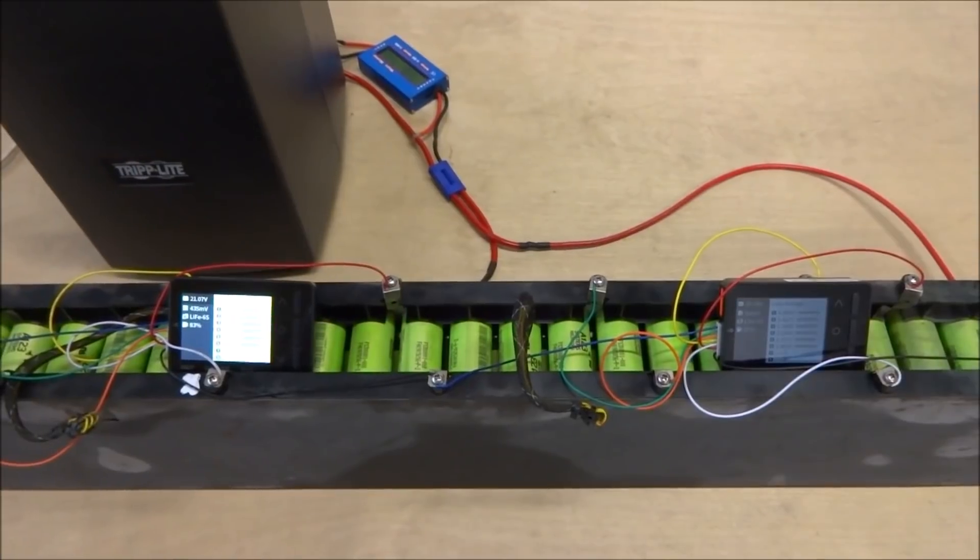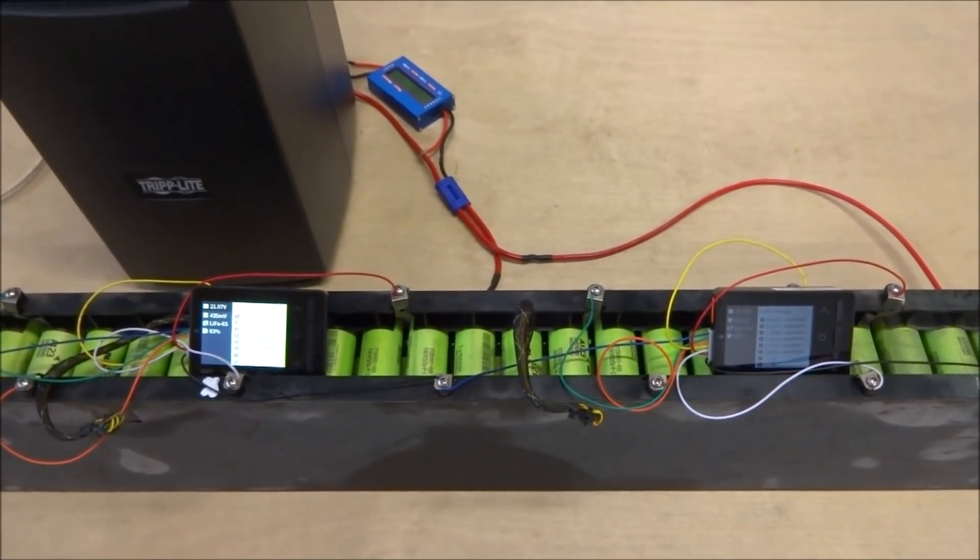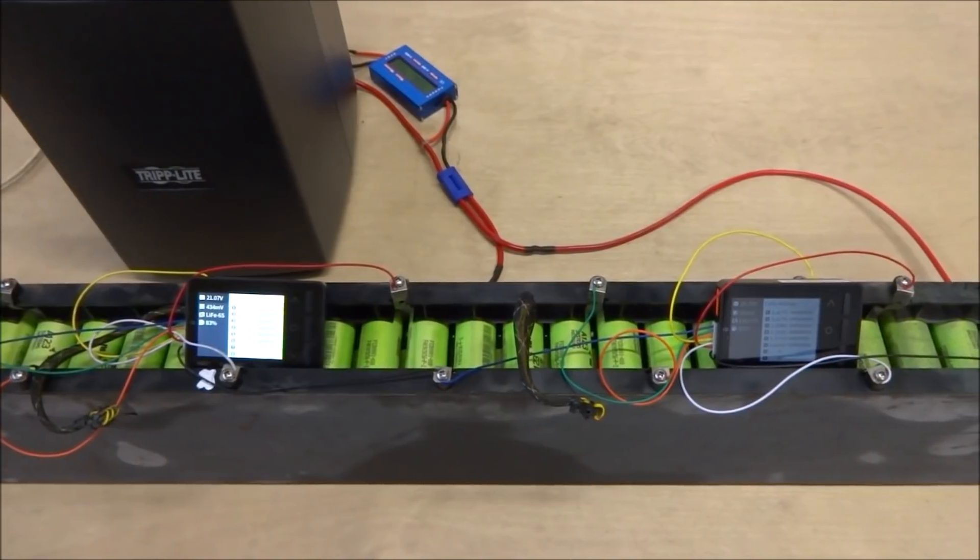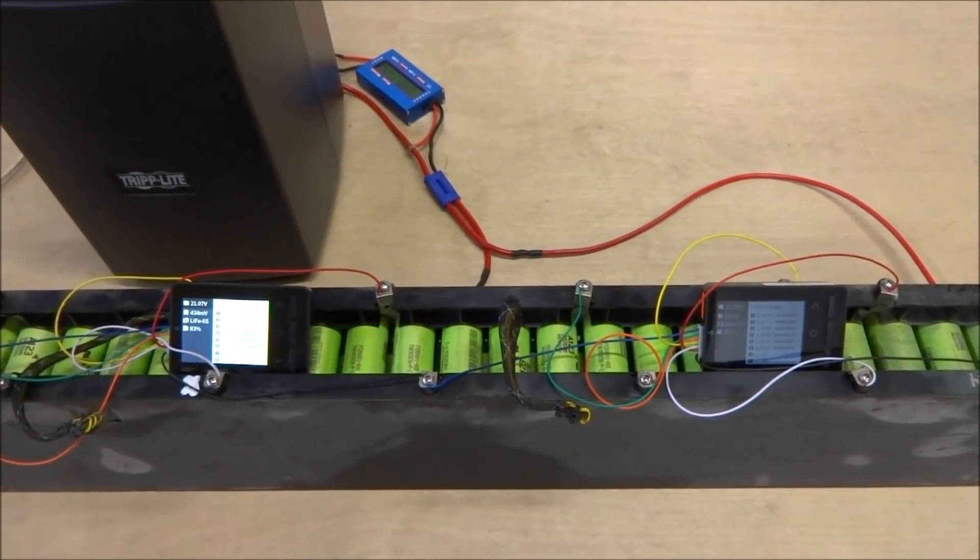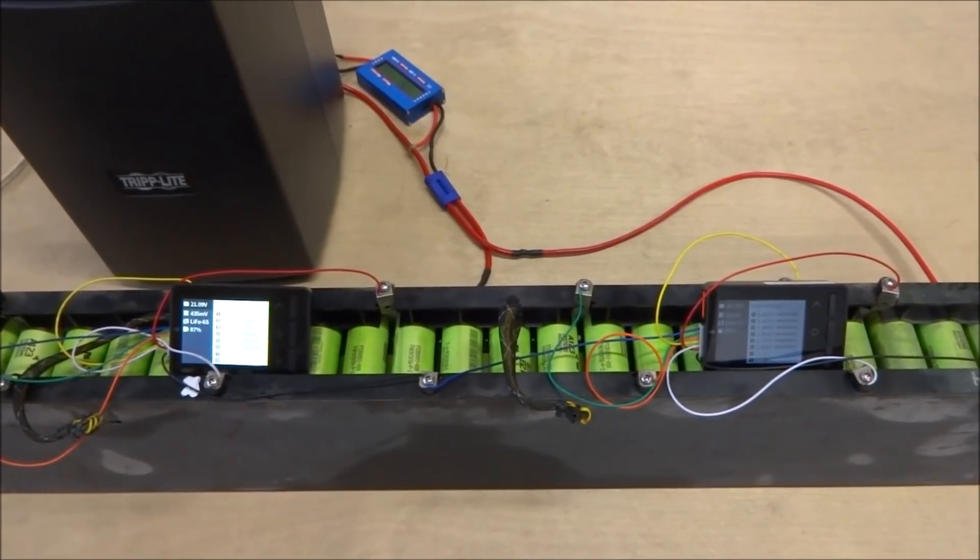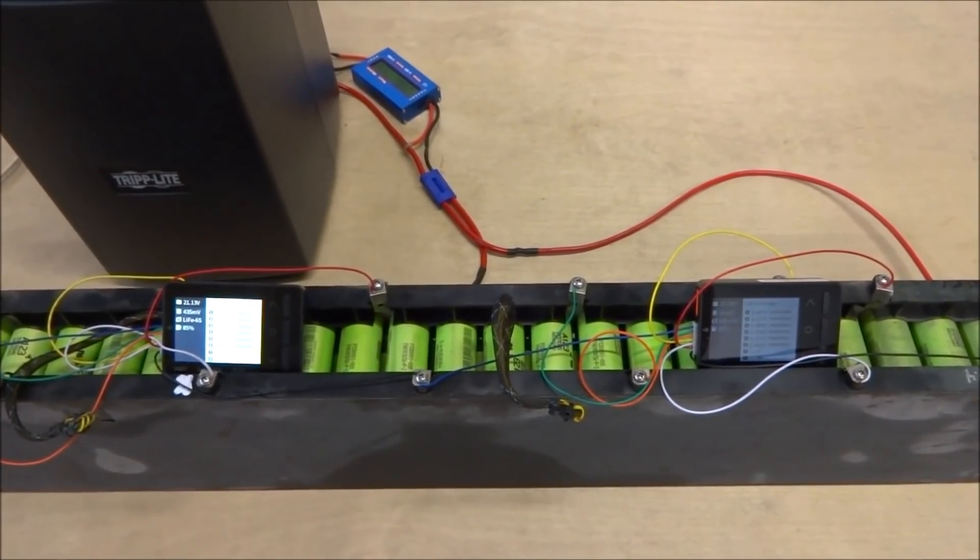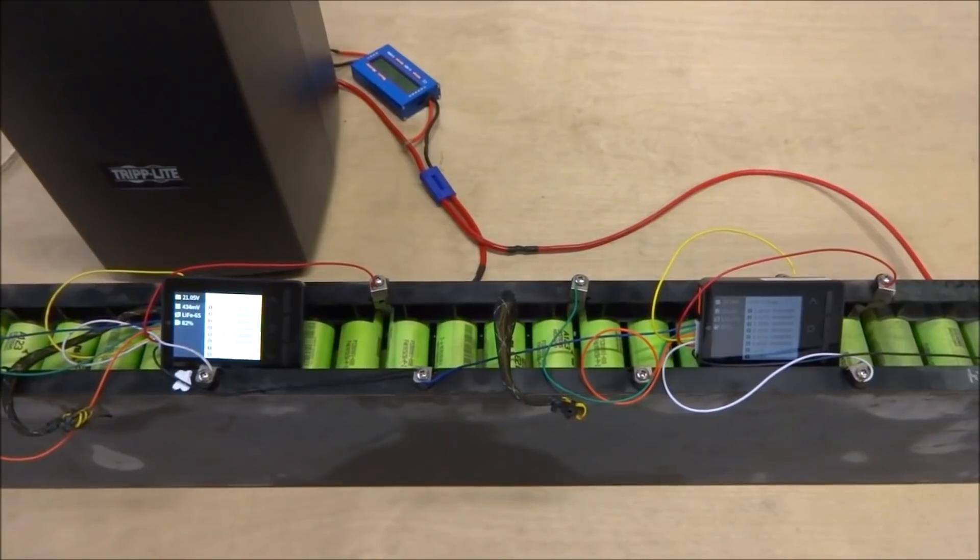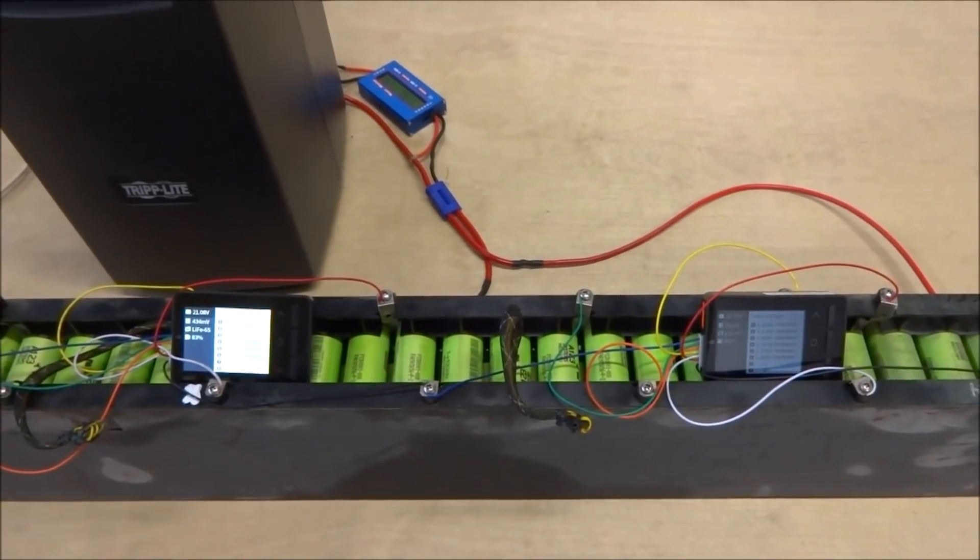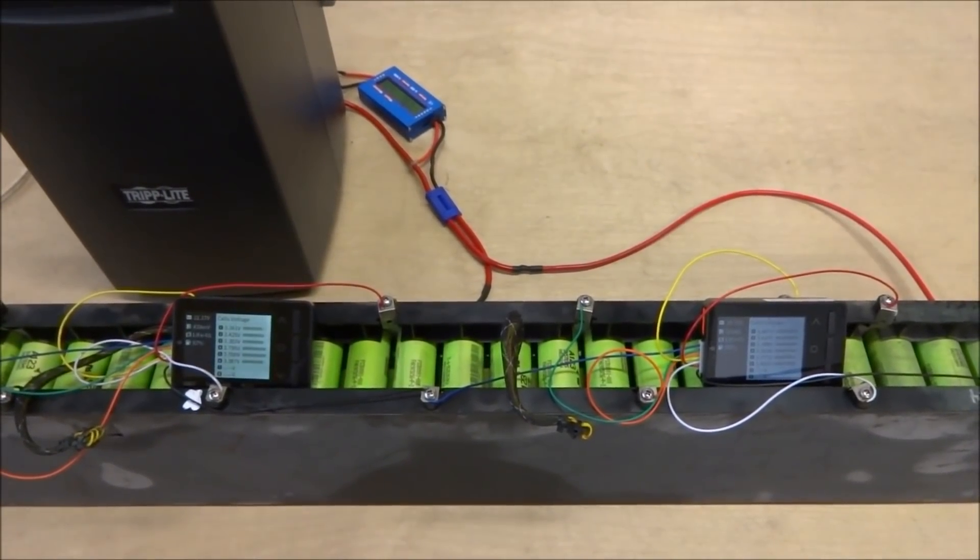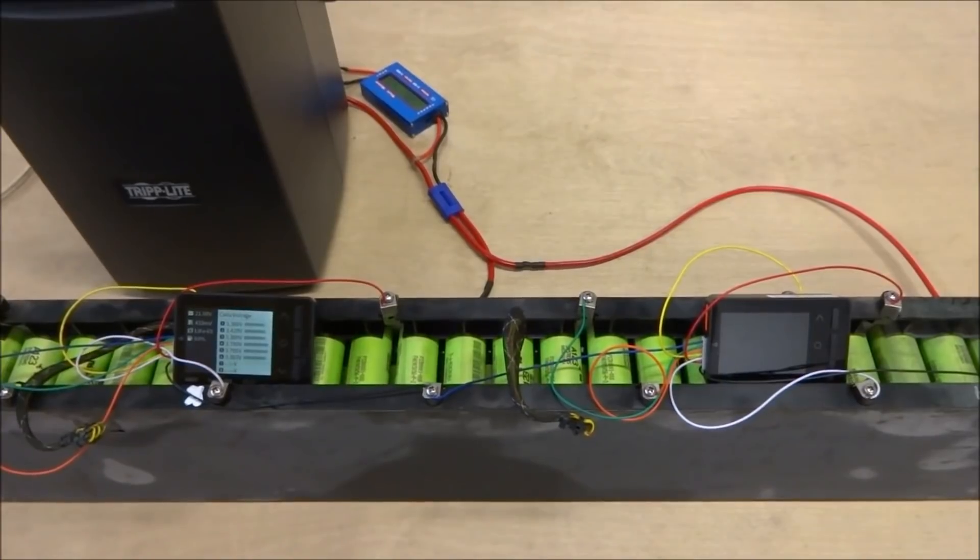So ideally, I guess for UPS's a top balance would probably be better because you will very rarely be going down to zero voltage or fully discharging the batteries, only when there's a long power outage. Most of the times the cells will be sitting at a full charge level, so I think what I will do is go ahead and do a discharge test and then recharge the batteries and balance them at the top.